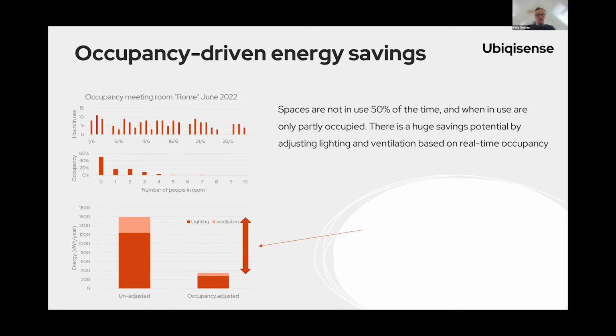Now if we use a people counting sensor to control the light and also control the ventilation based on the number of people in the room, there's a really big savings potential for a single 10-person room like this: up to 1,250 kilowatt hours per year.